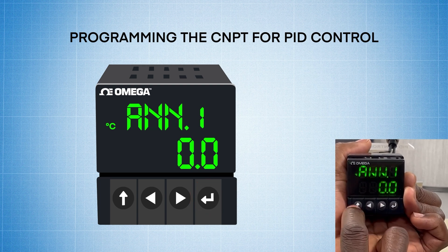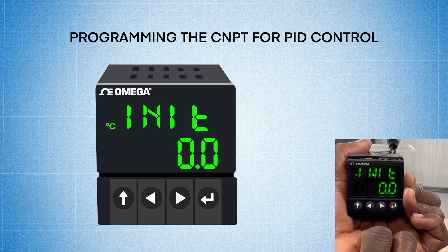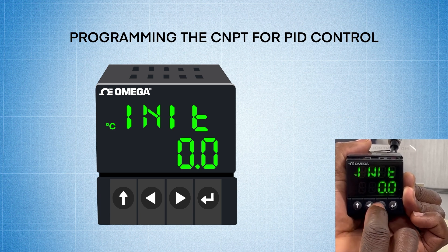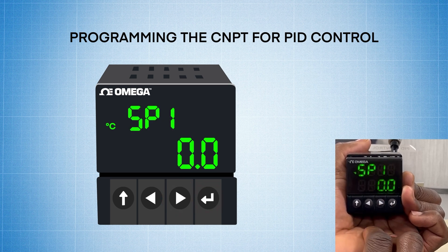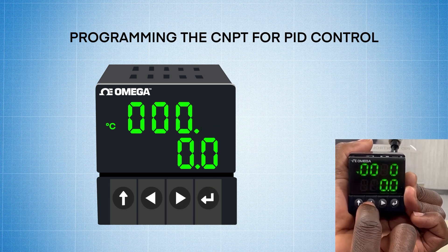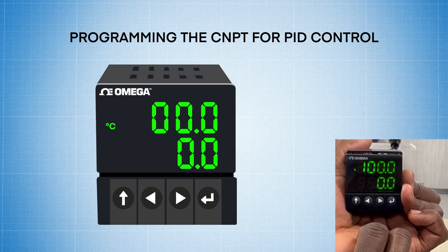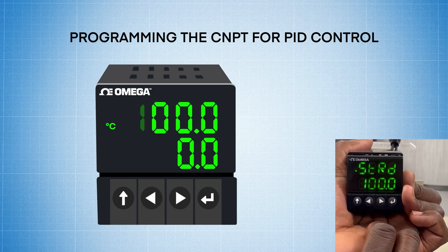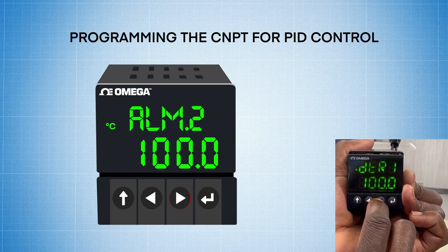It goes back to annunciator 1, and now I'm going to press the up arrow once, twice, to go back to initialization. Now we need to program the set point, so I'm going to press the right arrow, go to program, and press the enter key one time to go to set point 1. Now I'm going to select set point 1 by pressing the enter key, and I'm going to press the left arrow because I want a set point of 100. I use the left arrow to move the digit, right arrow to change the digit, so I'm going to change that to 100.0, and now I'm going to hit enter to store that.